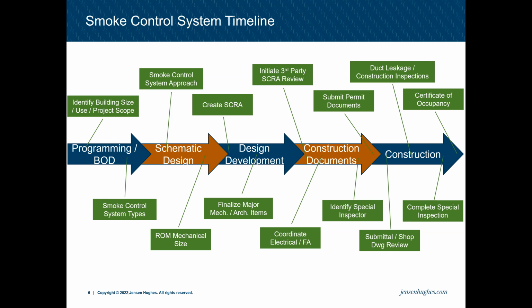Construction is more like the design does start to take a back seat, obviously, and it's more responding to special inspection comments and stuff in the field. So in construction, special inspection is really the heavy scope for smoke control. With that, there's going to be submittal and shop drawing reviews, duct leakage testing, construction inspections, and functional testing. Near the end of construction, special inspections should be completed. Ideally, it's completed a couple weeks before you are planning for a certificate of occupancy, so that way you have some time if something does come up during special inspection.